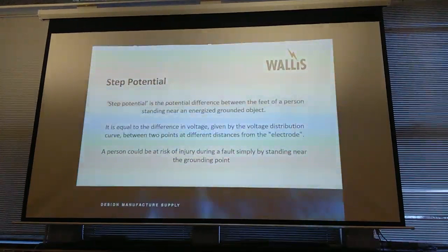Step potentials, very much the same as touch potentials, but it's the potential difference between your feet. So you're only really interested in what's a metre and a half, something like that. So it's the difference in potential between your legs. And as I was saying, if you inject a fault current into the ground just there, it will decay as it comes away from that point of injection. So because you've then got differences in potential across the ground, you will have differences in potential across your feet.